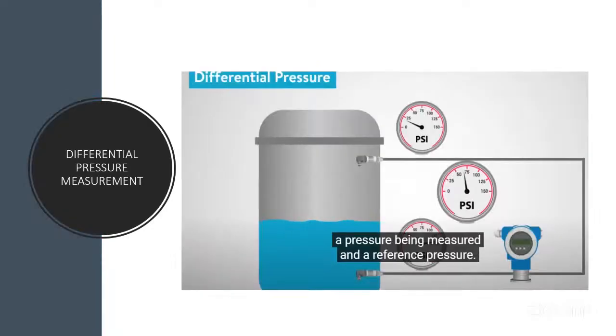The third type of measurement I was talking about has to do with differential pressure measurement. This one is clear enough in the sense that we measure the difference between two pressures, and the reference one, as shown in the picture here, is what is being captured. We only take measurement of two: the actual one we want to measure, and the reference one, and then we have the value of it all.